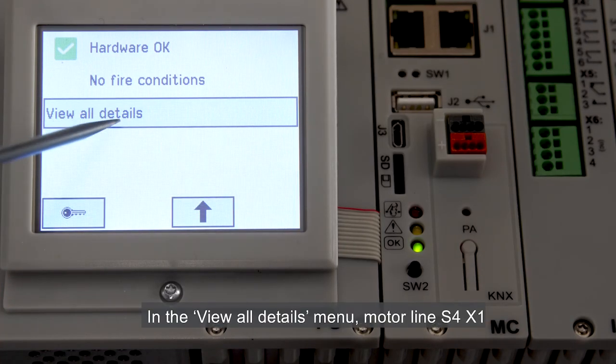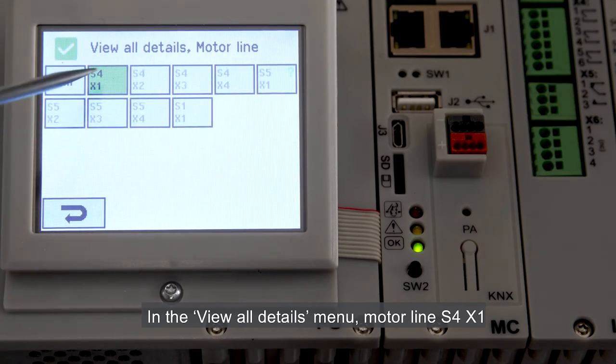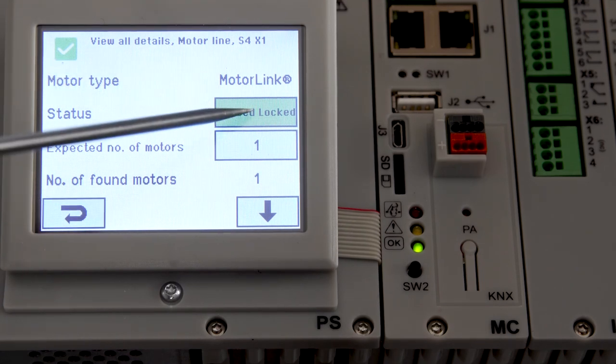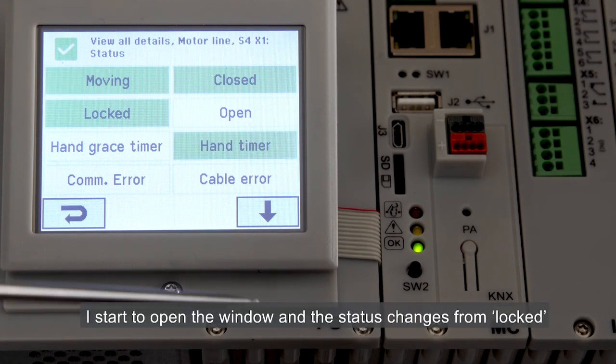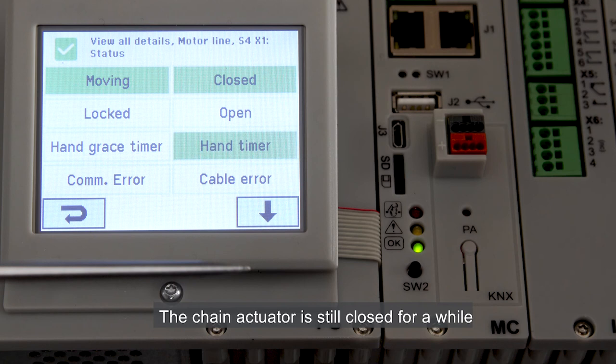In the View All Details menu, Motor Line S4X1, we can see the status of the motor line. Now we see that the window is closed and locked. I start to open the window and the status changes from locked to moving. The chain actuator is still closed for a while until the locking actuator reaches a fully open position.